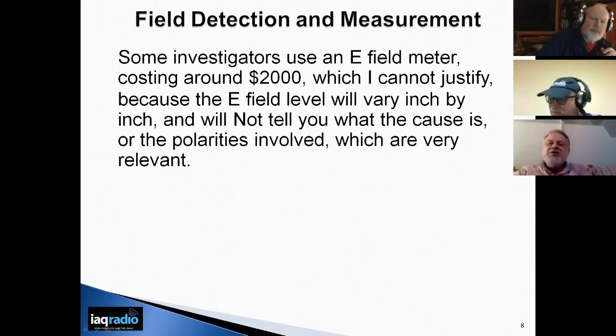...or whether you're in the most distant room from that panel, where there may be only one or two cables, the electric field can vary dramatically between the two rooms. In the room farthest from the panel, with only two cables, you can easily tell what's going on, whereas in the room by the panel, with all these sources scattered about at different polarities, as you move the meter even a few inches, that field level will vary, and it really doesn't tell you what's going on.